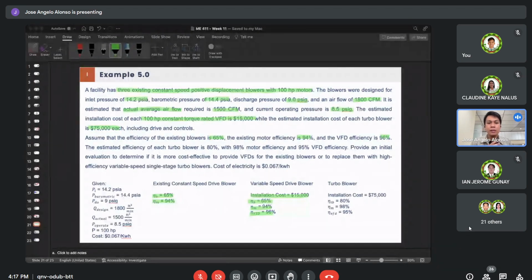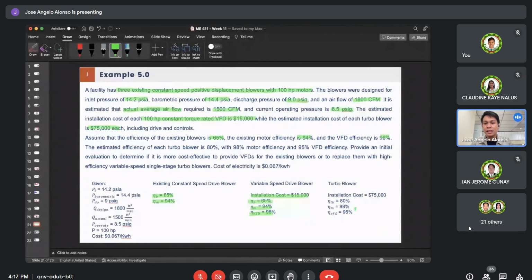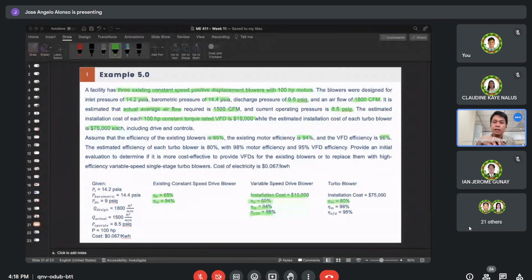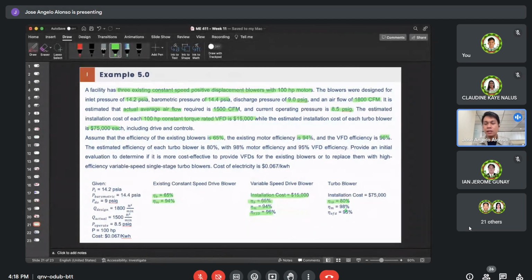When we install the turbo blower instead, the efficiency of the turbo blower is 80%. When we install this, class, we replace the existing motor and existing blower, immediately replacing everything. So it has its own efficiency. The blower now has its own efficiency of 80%, which is definitely higher.